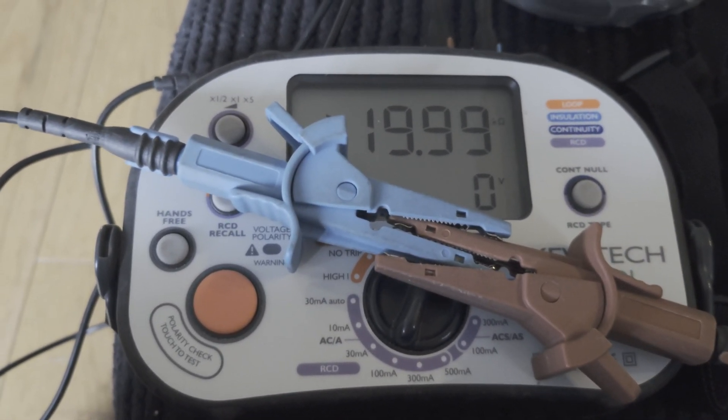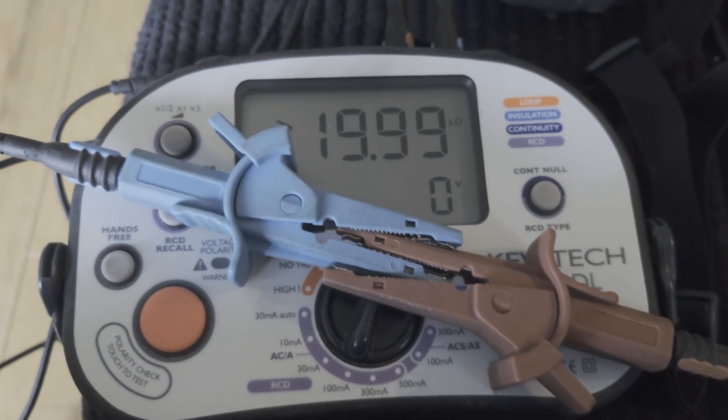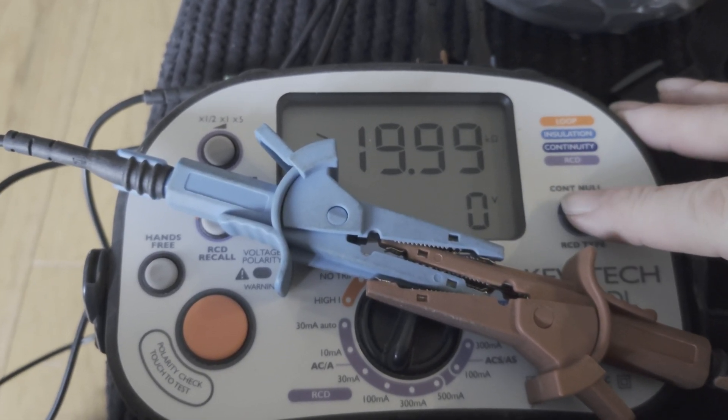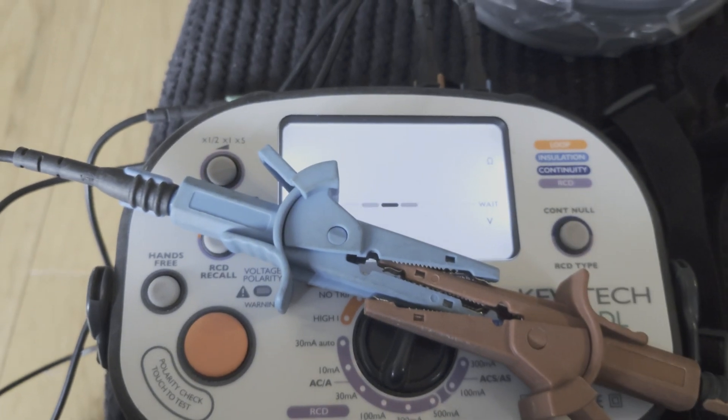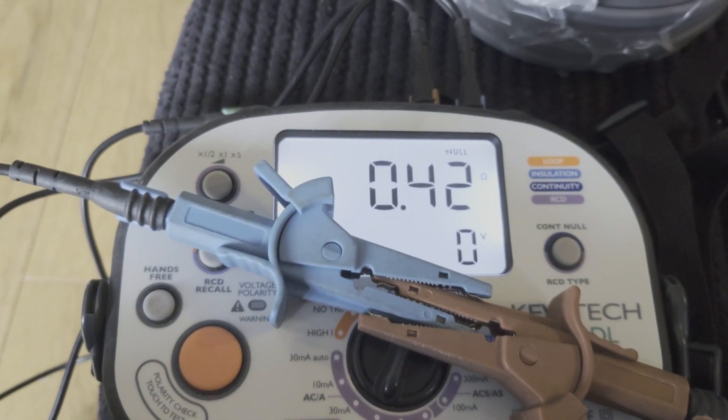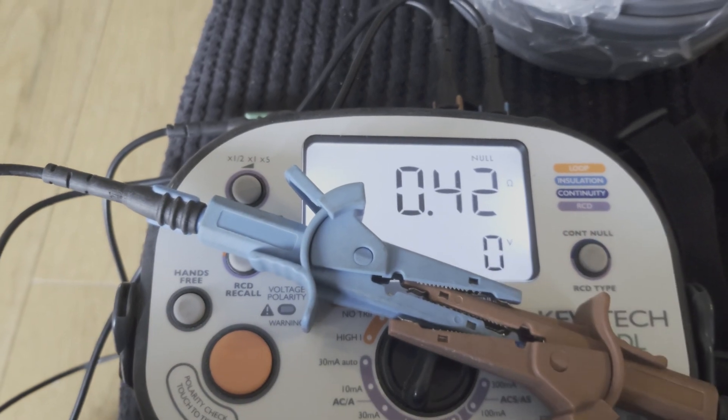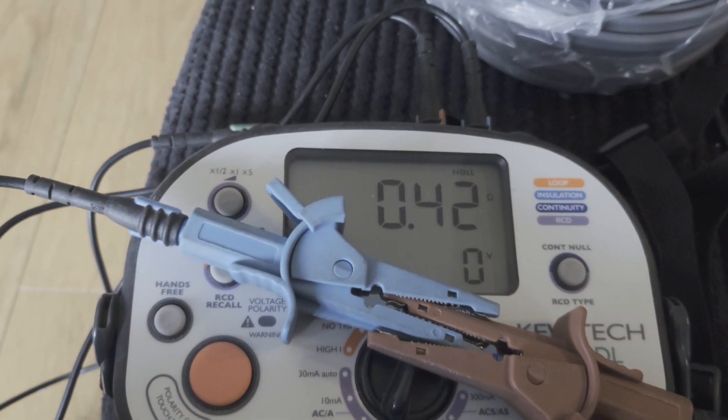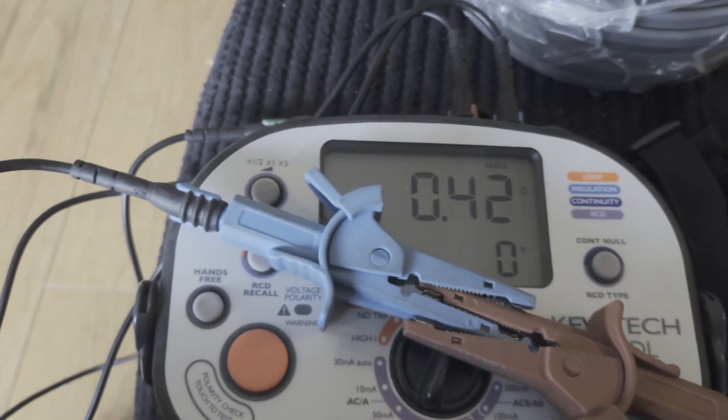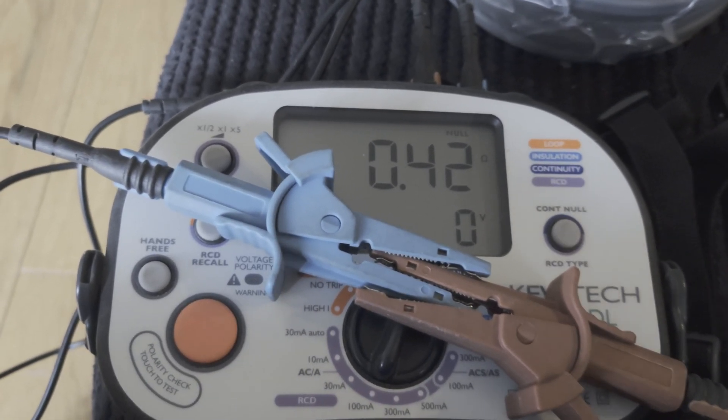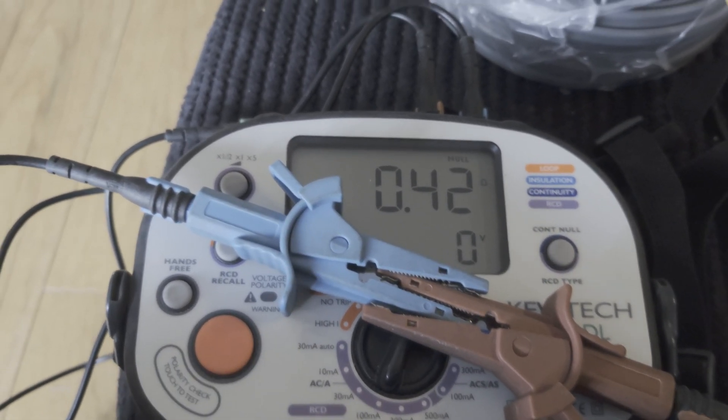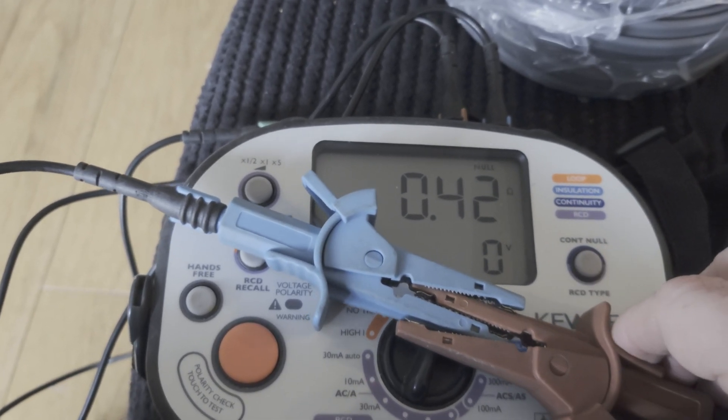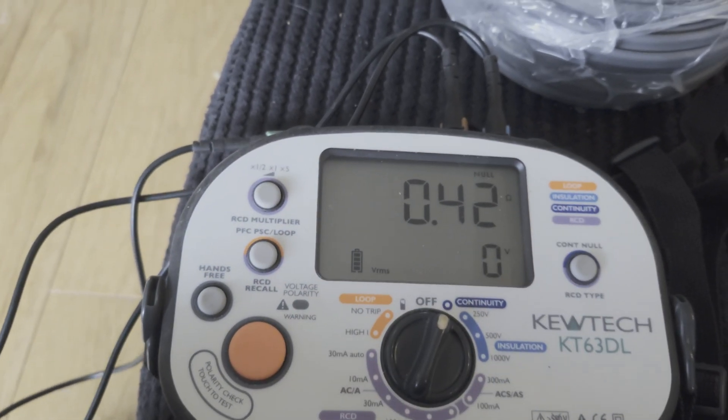Now you see that's how I've connected up the crocodile clips. So I'm going to press the null button. It gives me a reading of 0.42. I know if I get a reading somewhere between 4 and 5, then I've nulled these leads correctly. That's how I know. It'll probably be different for any other test equipment, but that's how I know. So that's now been nulled, so I'll disconnect those.